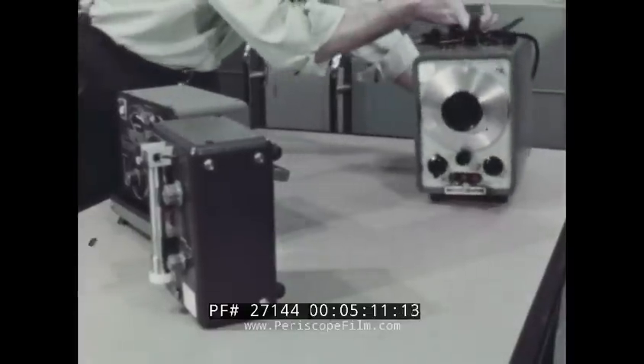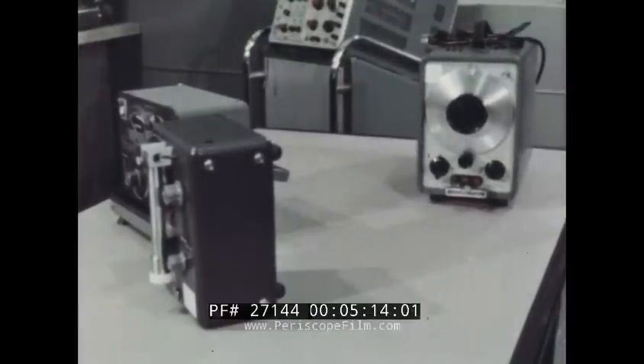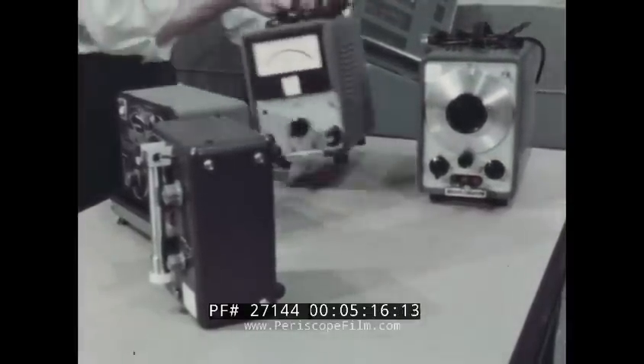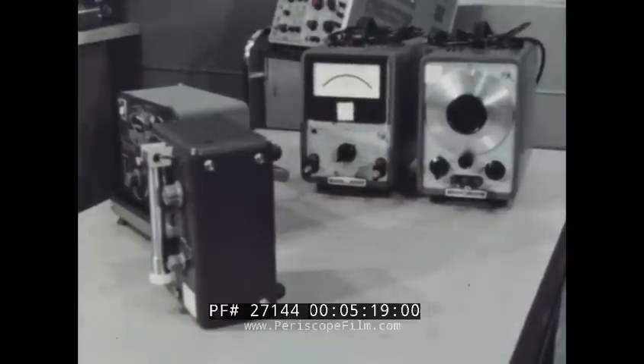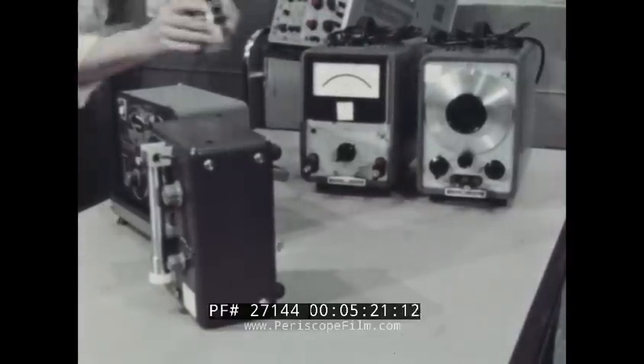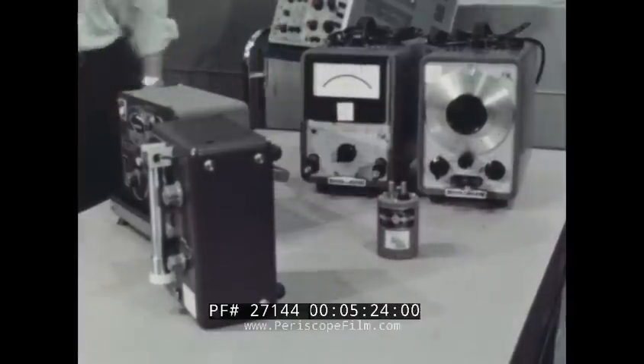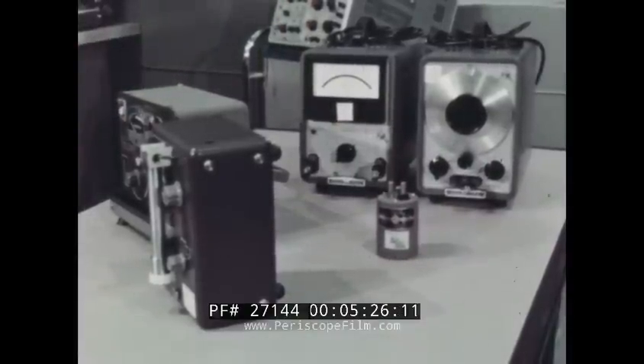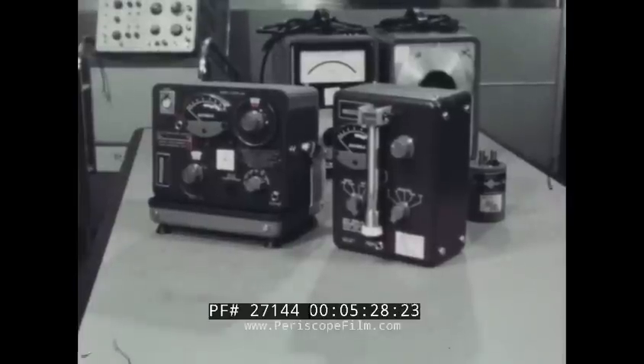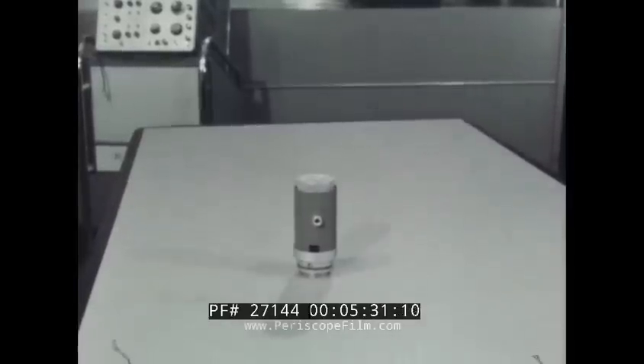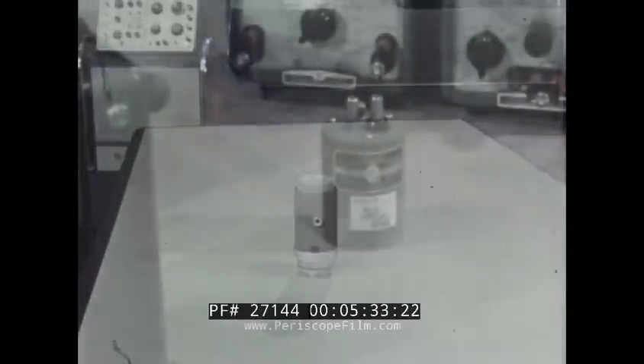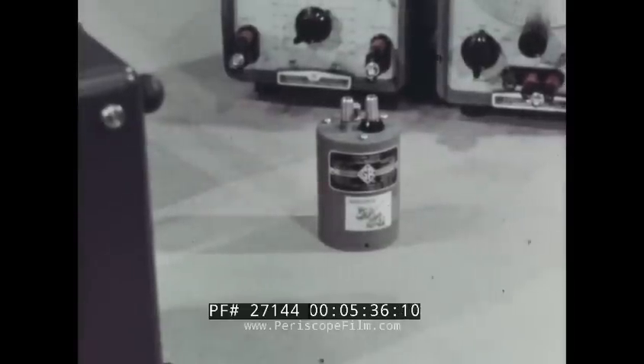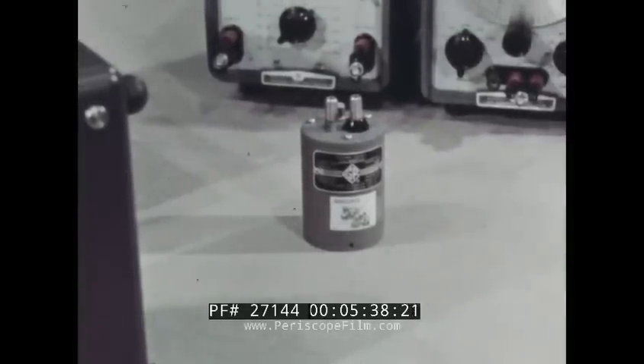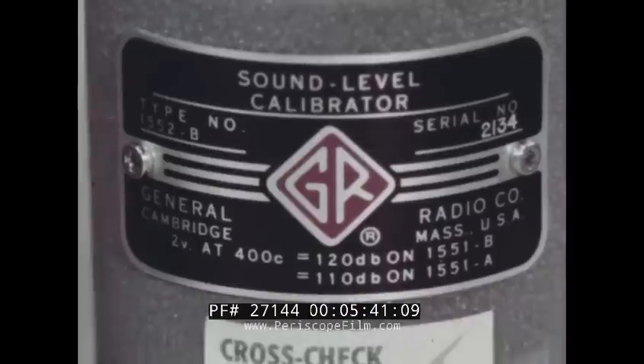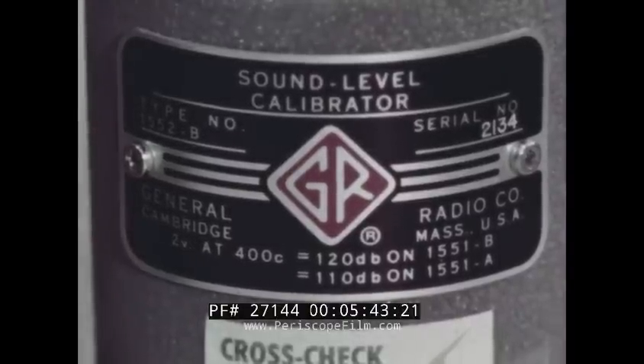You'll need an audio oscillator, a voltmeter, and a device called a calibrator, which feeds the audio signal into the microphone. One instrument available for this job combines all these items into a single unit. The calibrator is labeled to show the frequency and voltage it's designed for. In this case, 400 hertz at 2.0 volts. The unit hertz, of course, is what used to be called cycles.